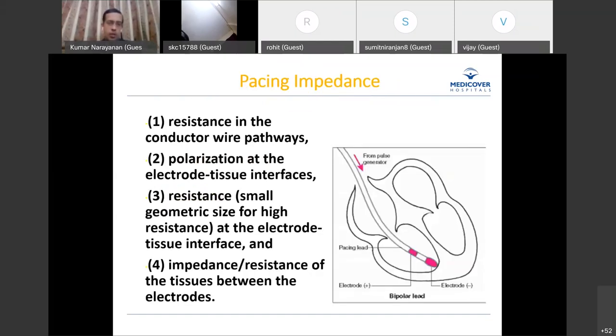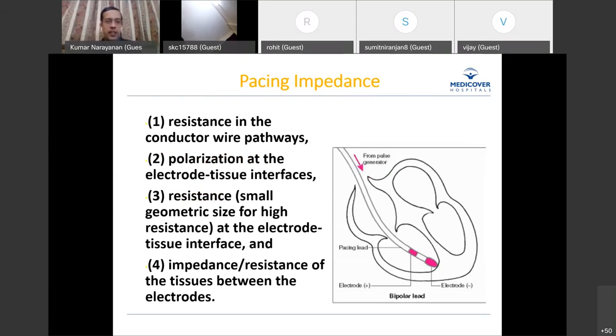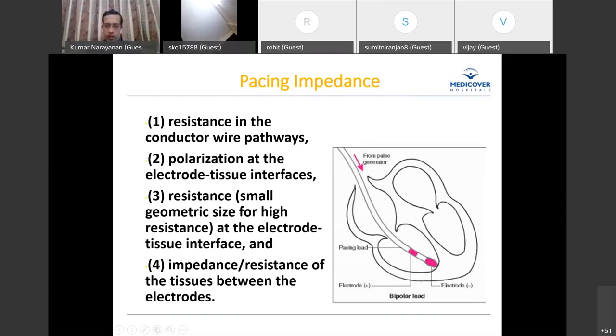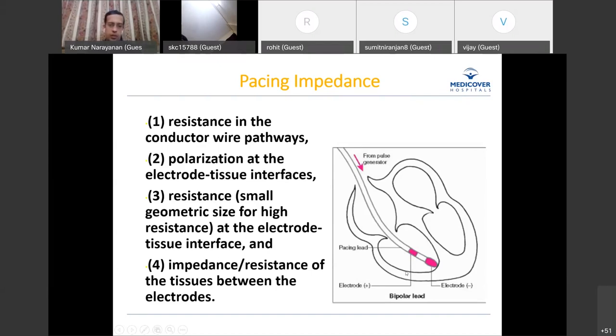The components of impedance include: the resistance in the conductor wire pathways; polarization at the electrode-tissue interface; the resistance at the electrode-tissue interface; and some tissue resistance between cathode and anode. The cathode and anode are at the electrode tip, and various processes happening at that interface contribute to the resistance as well.